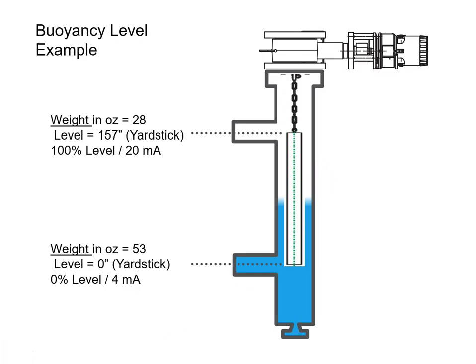With buoyancy, it's the same concept as DP level. The instrument measures the buoyant force or weight of a displacer — we're actually measuring the force or weight and we're inferring the level off of the force or weight of this displacer. In this example, when we see the displacer is lightest at 28 ounces, we have a level of 157 inches. At the lower level, we're set up to measure 53 ounces, which converts to 0 inches.